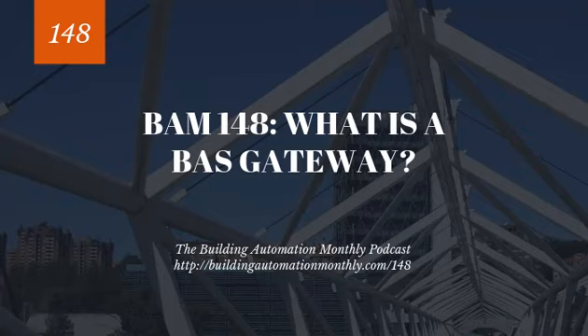So what are BAS gateways? Well, if you think about it, supervisory devices like JACEs, NEs, PXCs, they all are gateways. Ultimately, supervisory devices are the third layer, or the second layer, of the building automation 4-tier architecture. So it goes servers, supervisory devices, field devices, and inputs and outputs. Supervisory devices have existed to take field level data and convert it into network level data.